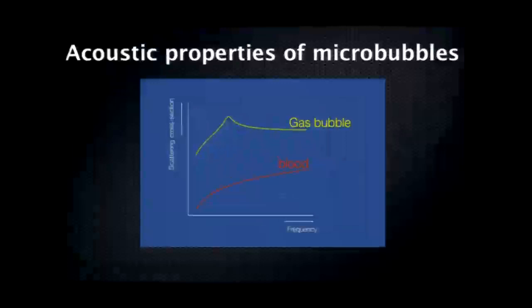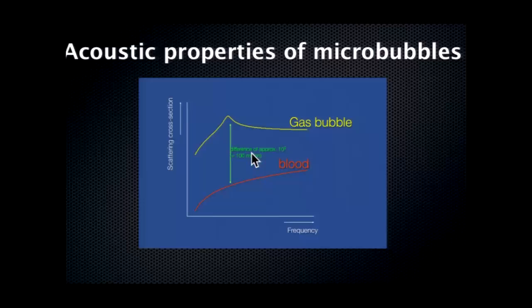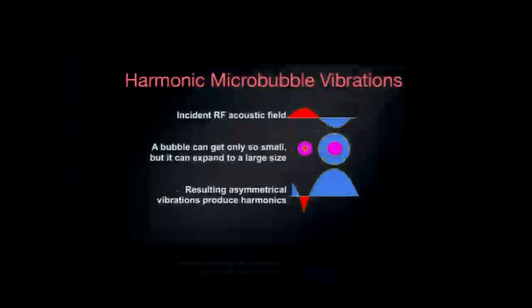And realistically, we need it to have a diameter of about four microns to be safe. But even if we take a bubble of that potential diameter, there is a huge increase in terms of its backscatter from blood of the order of 100 million. So it ought to make it very, very easy to see. The problem is that when we're doing myocardial contrast echocardiography, the amount of contrast microbubbles that appear in the tissues themselves, in the organs, such as the kidneys or in the myocardium, is very, very small. So we still need to use very sensitive and complicated systems to actually detect them.